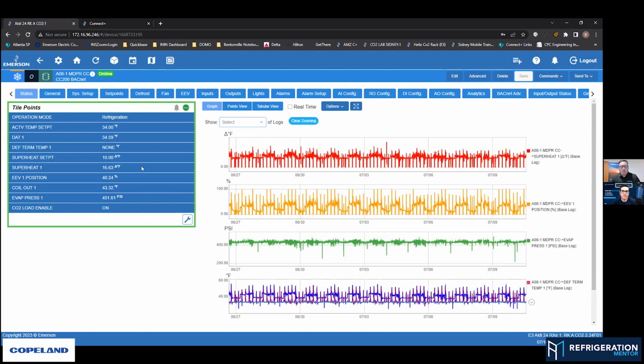For guys that haven't dealt with that before, it's a bit of a learning curve, but most pick it up pretty quickly. Our literature covers how to connect a case controller well, and then you've got all the case transducers and sensors that come up to the controller. 99% are landed correctly, but OEMs still have humans working case lines, so sometimes a probe gets mixed up and you have to check those things.